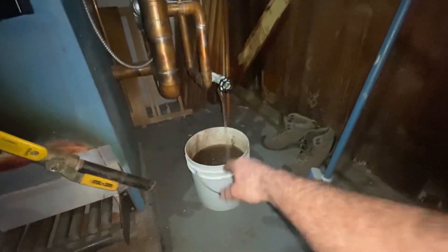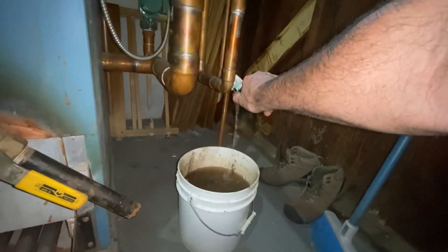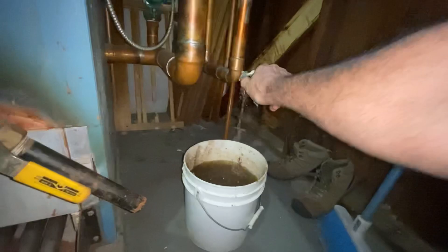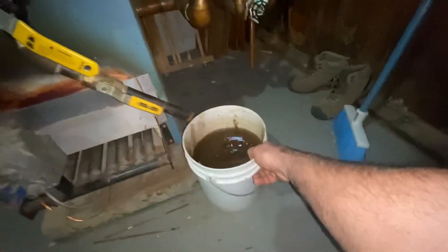I prefer the Hartford Loop to be coming down a lot more. But because it's old, it's going to stay there — it's not going to get repaired or changed or anything, because it's not causing problems. Not causing problems at this point in the game. This thing's got to be 30 plus years old. Just leave it.